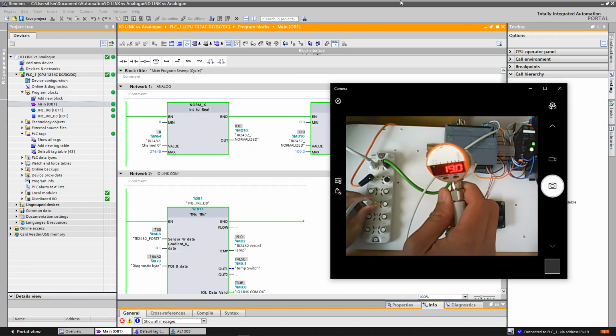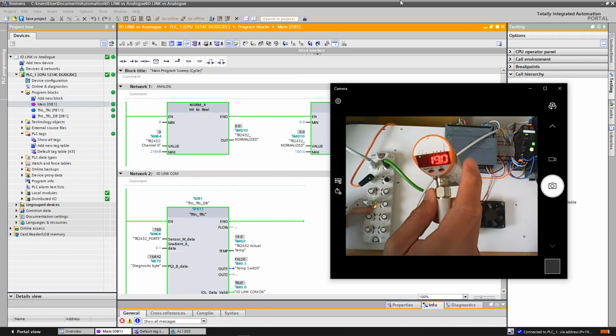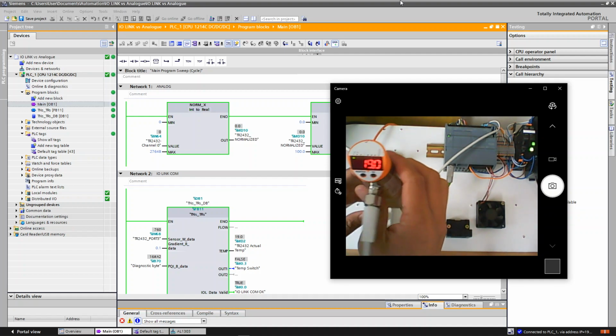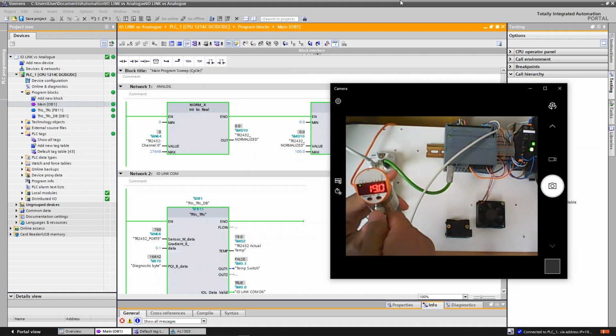So the parameters or the settings of this sensor can be stored directly into these ports, so you can activate that feature of the IO-Link master. So the next time you need to change a faulty or broken sensor, all you need to do is go to the warehouse or storeroom, get a new one, and put it in the system, and then you're back to production.